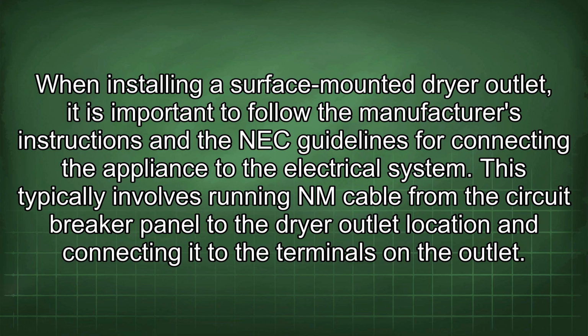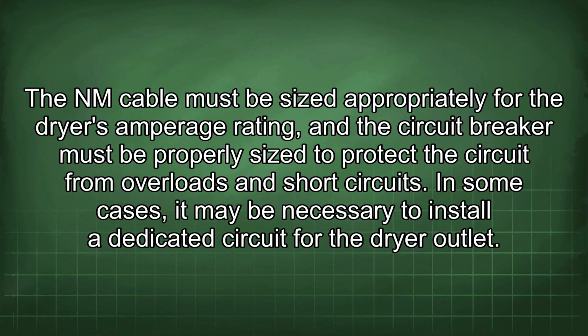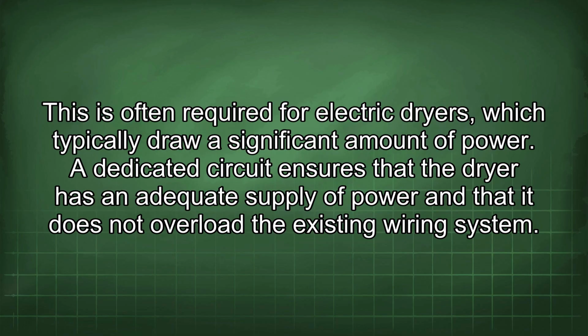This typically involves running NM cable from the circuit breaker panel to the dryer outlet location and connecting it to the terminals in the outlet. The NM cable must be sized appropriately for the dryer's amperage rating, and the circuit breaker must be properly sized to protect the circuit from overloads and short circuits. In some cases, it may be necessary to install a dedicated circuit for the dryer outlet. This is often required for electric dryers, which typically draw a significant amount of power. A dedicated circuit ensures that the dryer has an adequate supply of power and that it does not overload the existing wiring system.